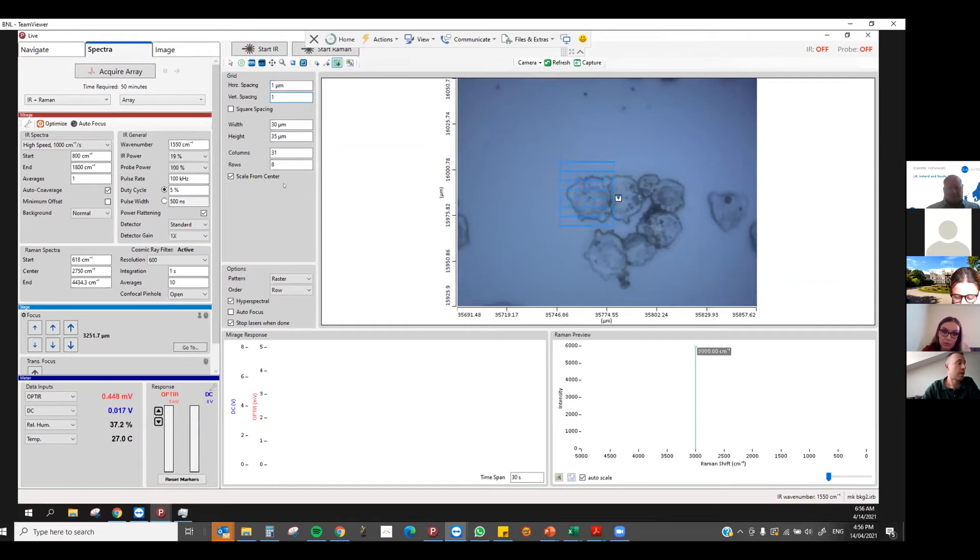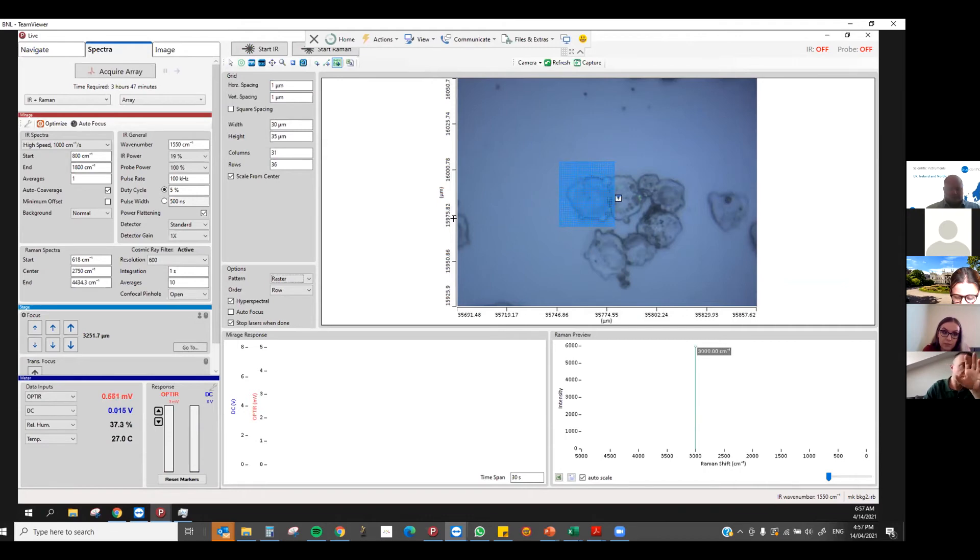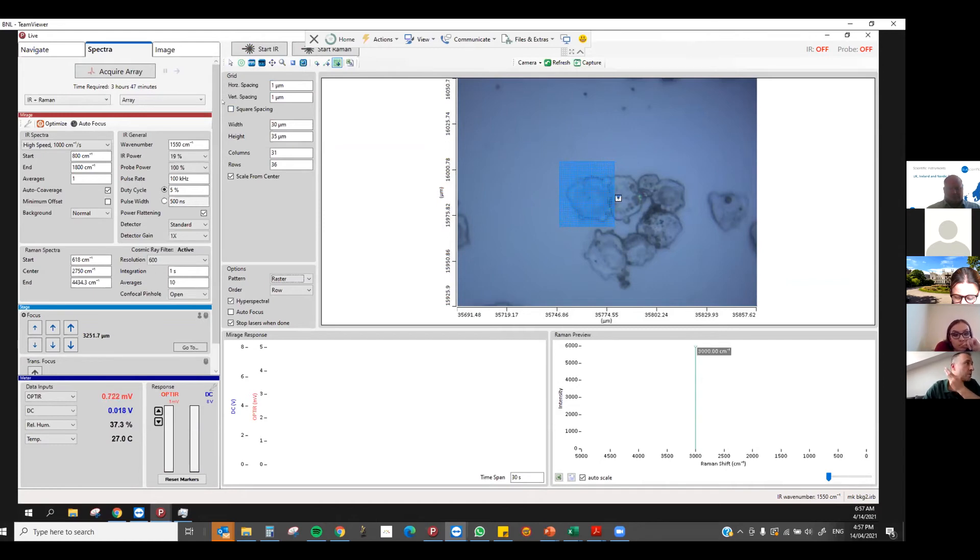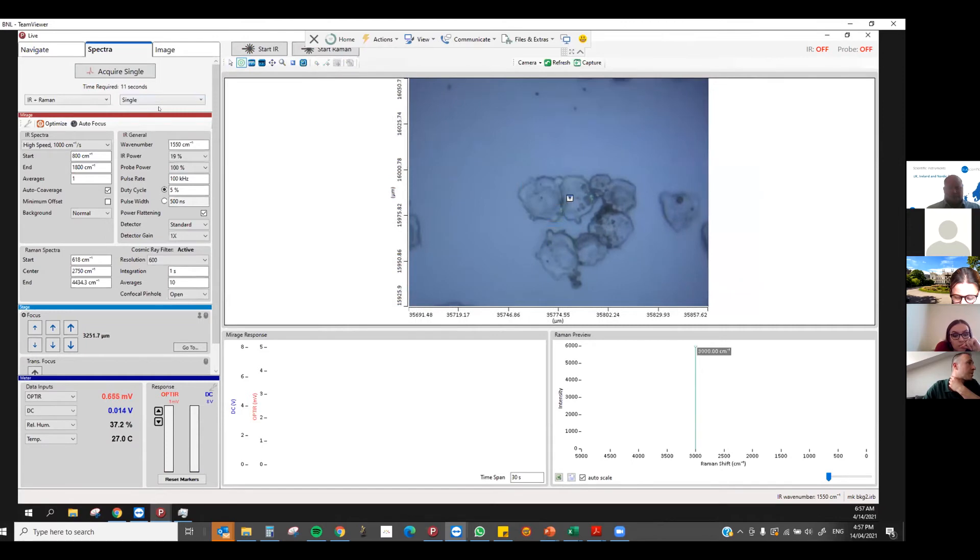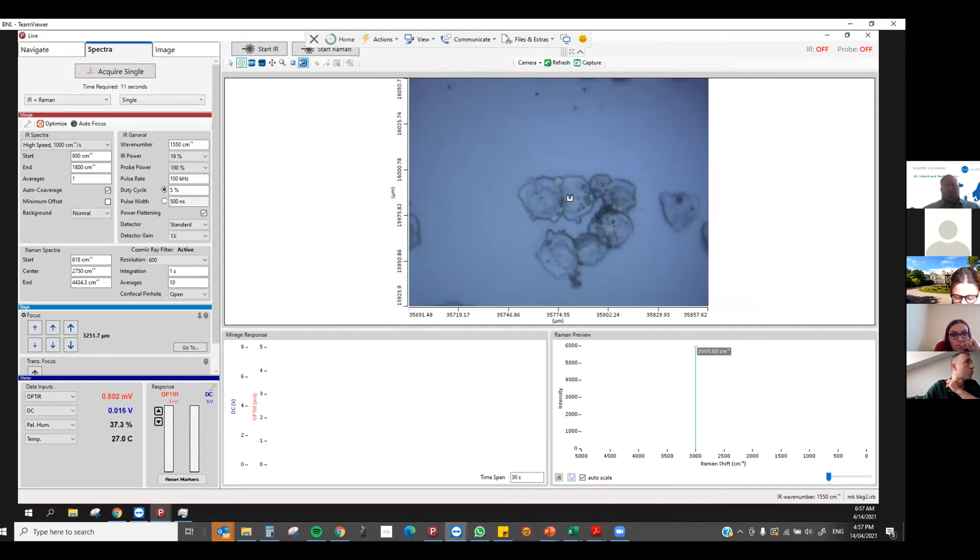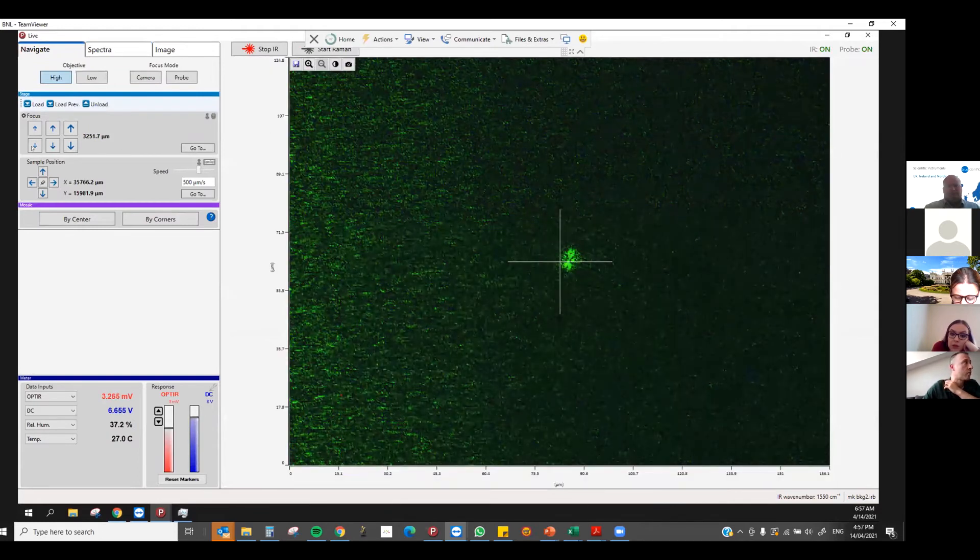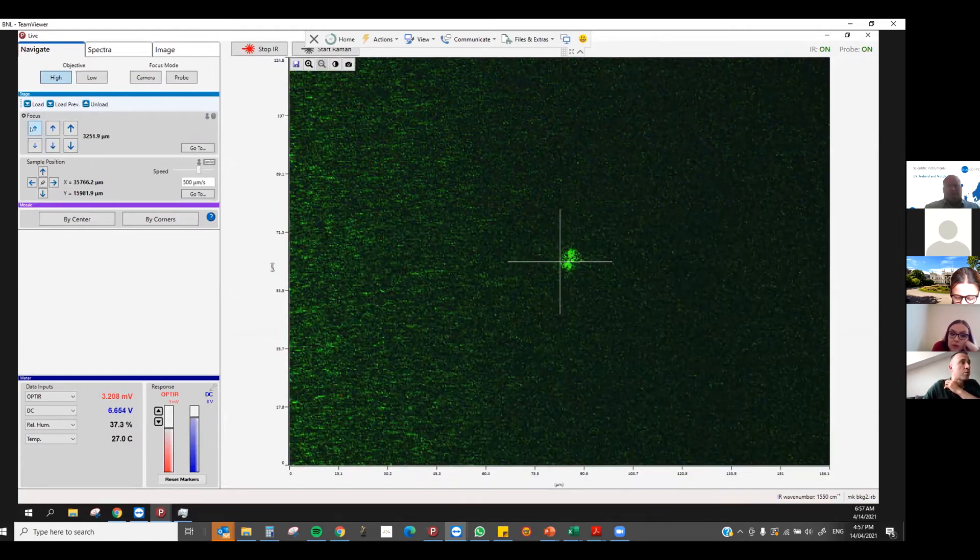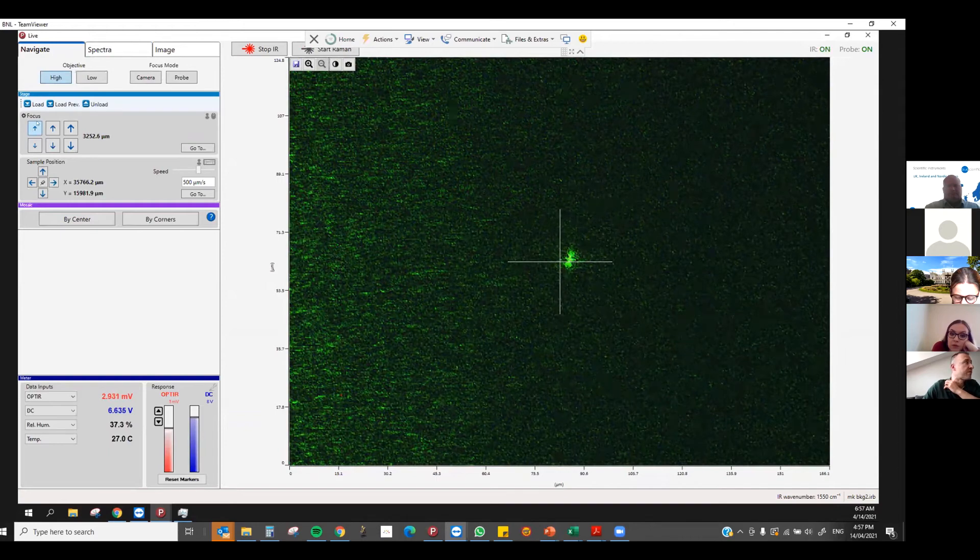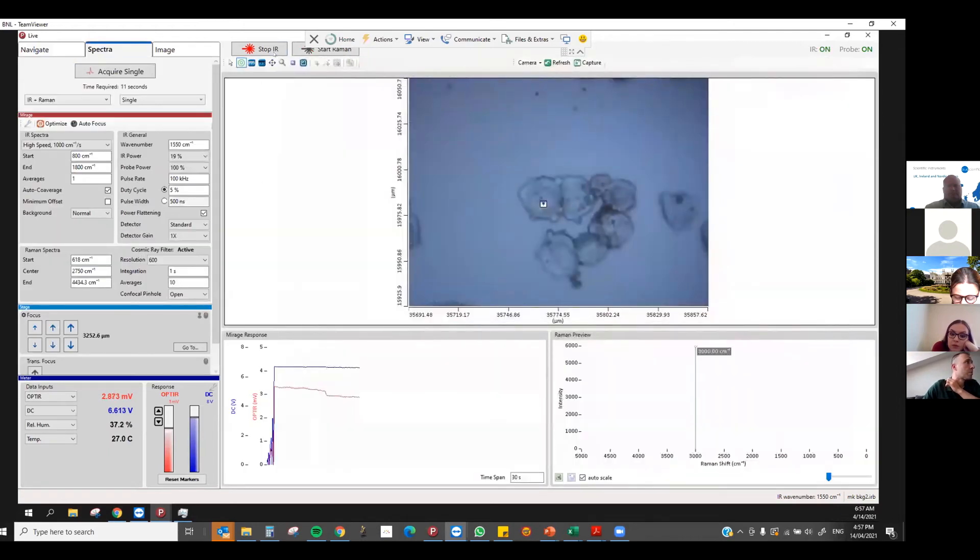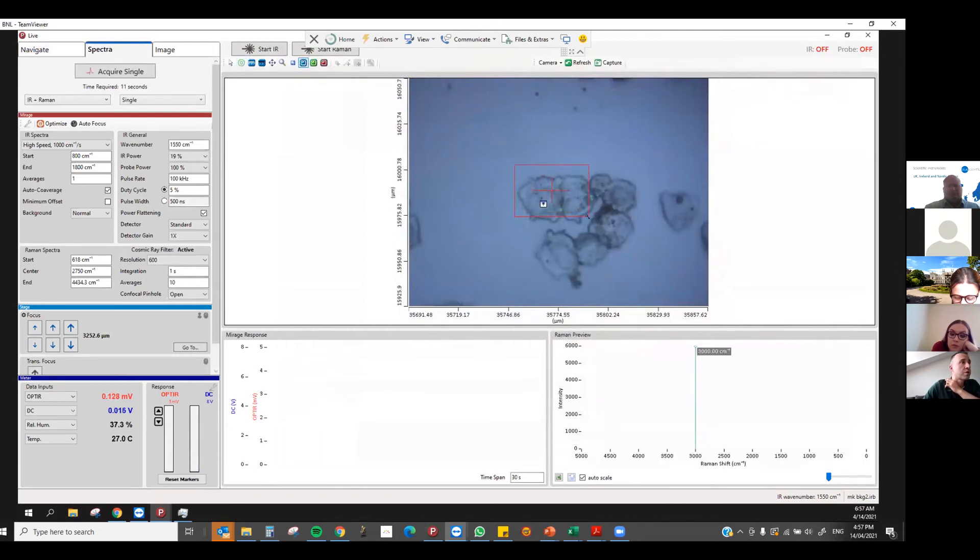You can collect an old-fashioned hyperspectral map. Both infrared and Raman will be collected simultaneously, so you end up with two data cubes, one for the infrared, one for the Raman, all collected simultaneously. It gives you an estimate of the time as well. In this case this would be about three-ish hour collect. Of course hyperspectrals take longer, but what we should take advantage of is the QCL with its single frequency collection capabilities. What I'm going to do is draw an image box. Let me click that and make sure my laser is nicely and tightly focused. With the laser on, anyone doing Raman would be familiar with using this to make sure your Raman is nicely focused. Let's stop that. Let's draw a box which represents our measurement area. Let's maybe measure both of these cells. Let's hit the green accept button.